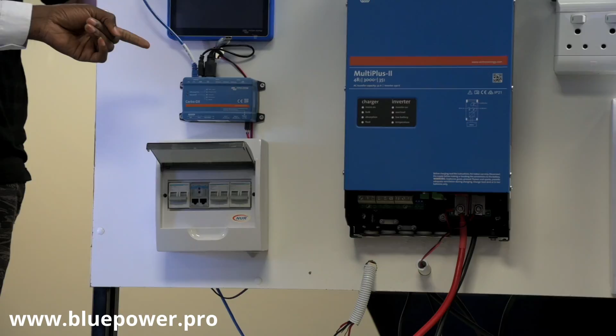So between the batteries, they run on a different protocol. I don't think they run on CAN, that's RS485. So the link between the batteries doesn't require a termination plug, it's just a CAN bus from the BMU to your GX device that requires one termination. The other termination plug is built in.